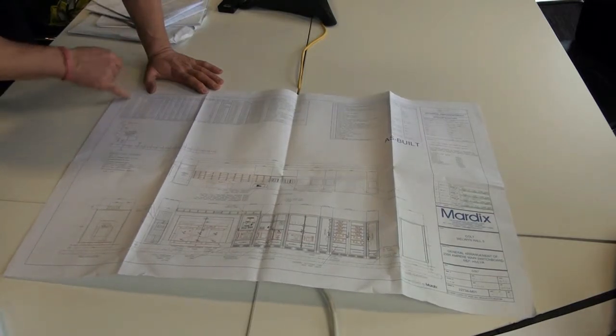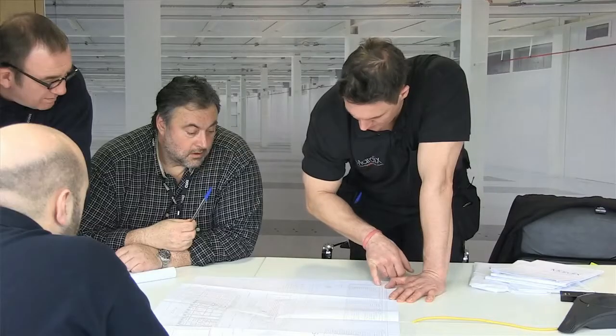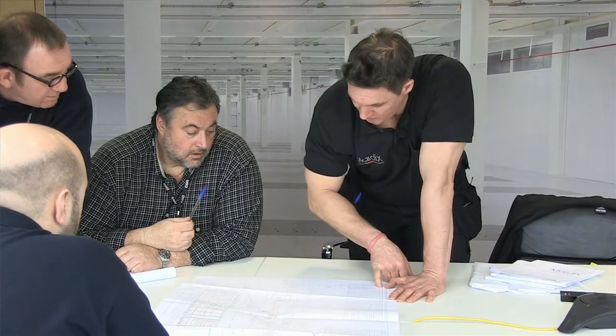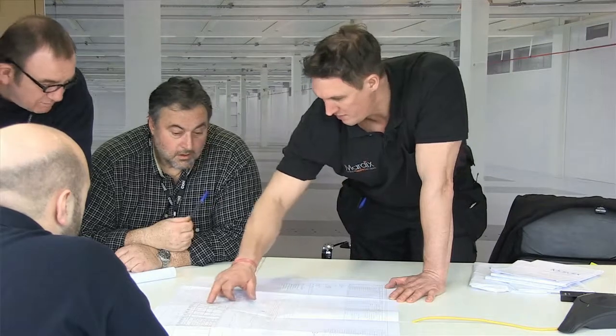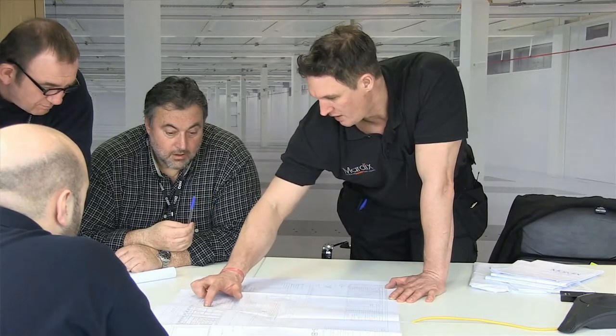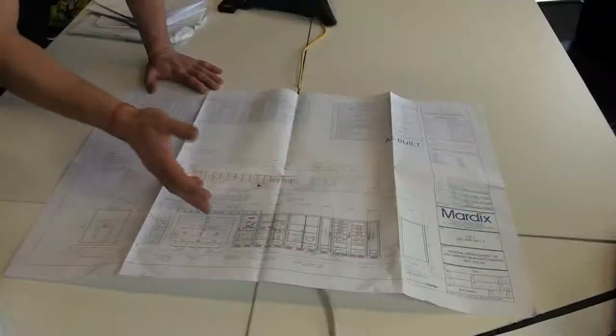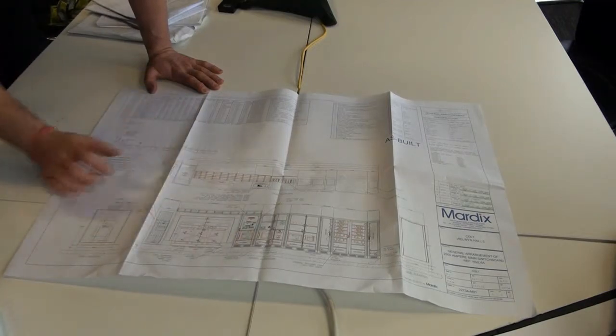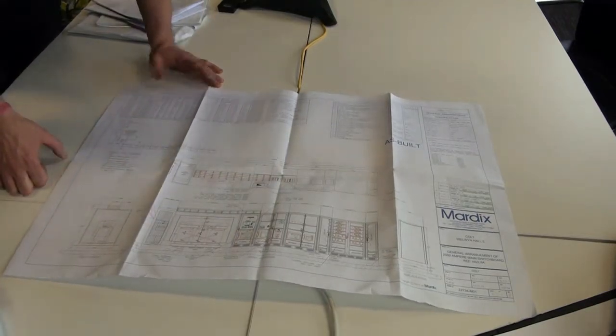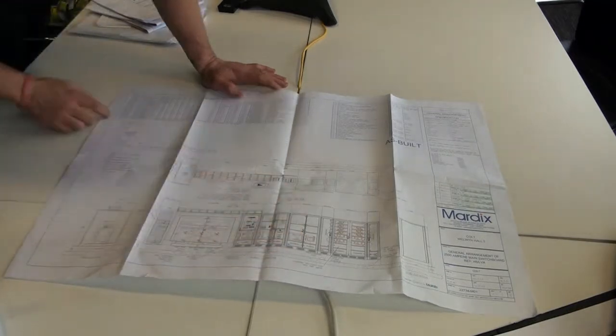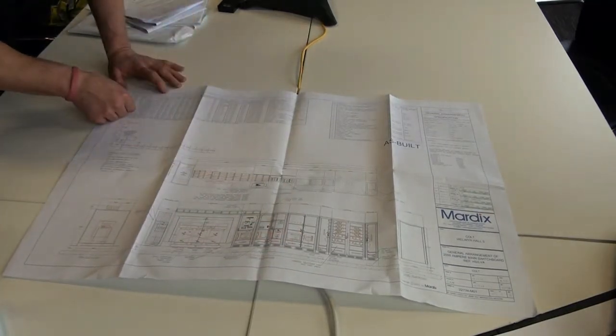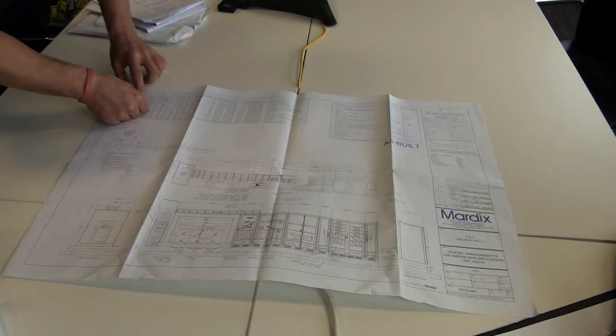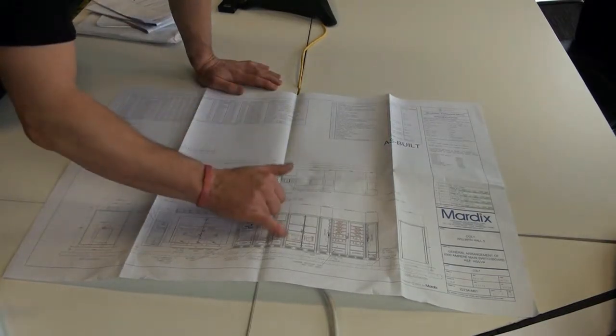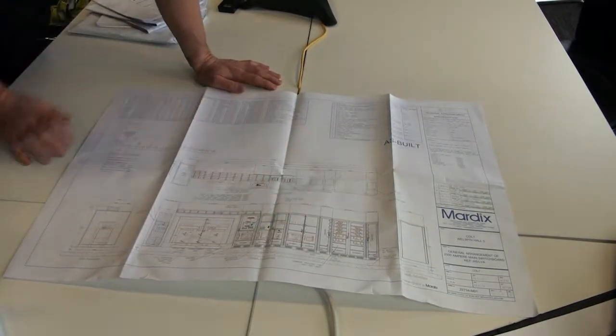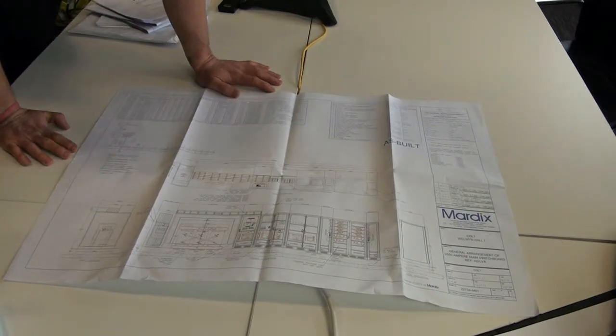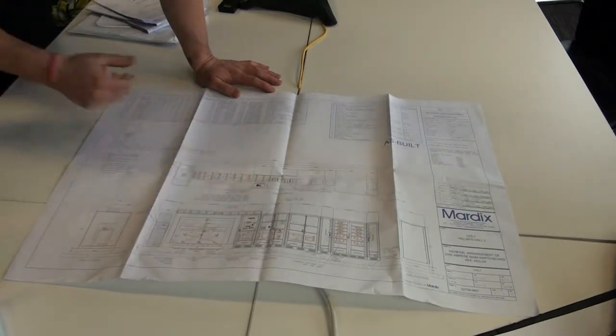So for instance, A1, 2,500 rated breaker. TPNN is three phase and neutral, which basically means it's a three pole breaker, and then it's got a neutral link down there. Again, when I get there, I'll show you that. That is different from A4, which is a four pole breaker, so that has no neutral link in it. I'll show you the difference between the two breakers. Not much difference in the operation of the breakers, it's just that there's a neutral link, and one's three pole, one's four pole.